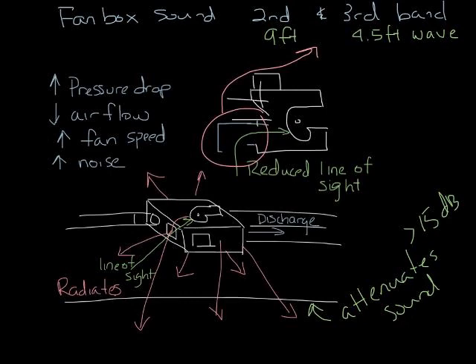When installing VAV boxes, you should mount them as high as possible above the ceiling. If you're within a couple of inches of the ceiling, it won't give you the attenuation you expect.